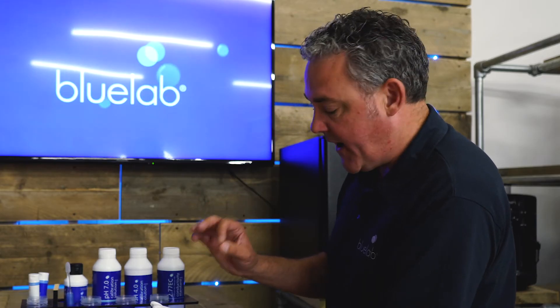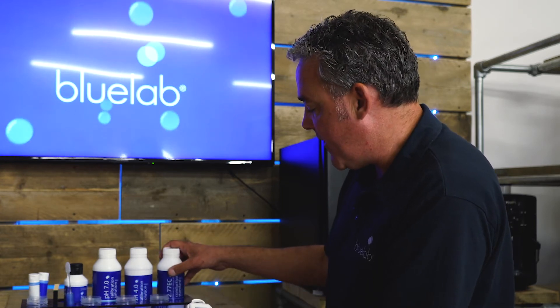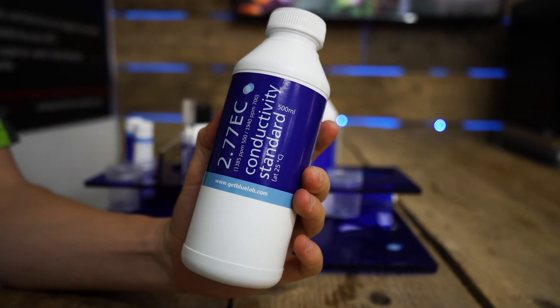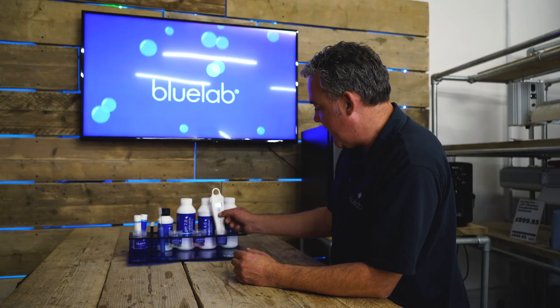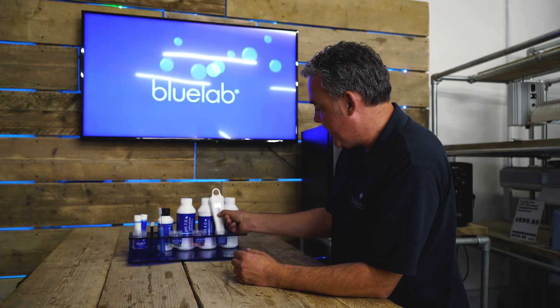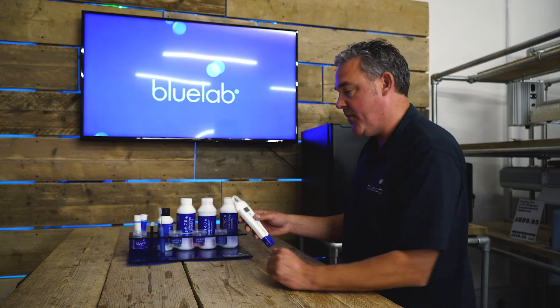You've got to be very careful. You've got to make sure that the probe is completely clean and you must calibrate in fresh 2.77 EC Bluelab solution. So you just put it into the Bluelab solution, let the reading stabilise, press and hold Cal — CAL will come up and then it will be calibrated. It should read 2.8.